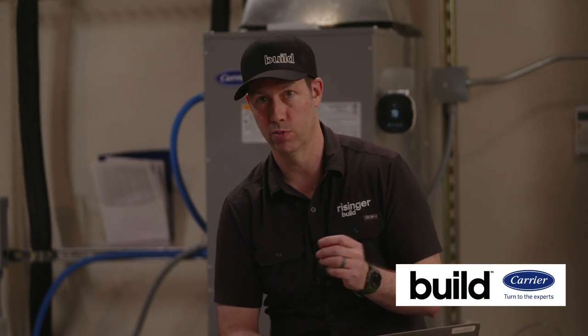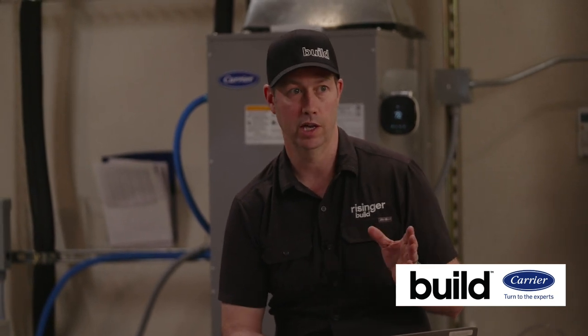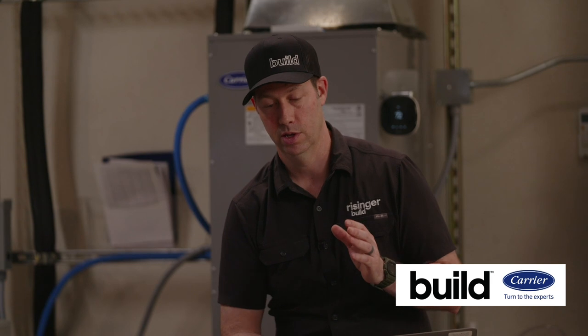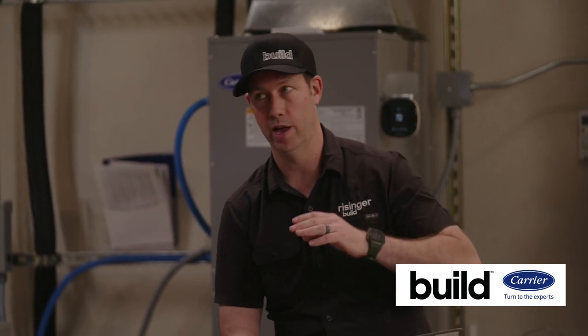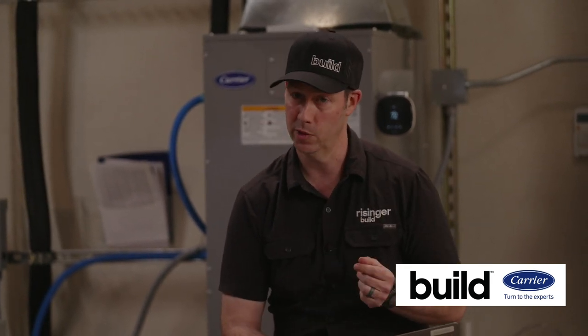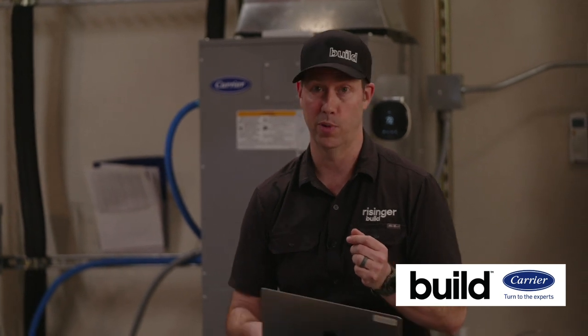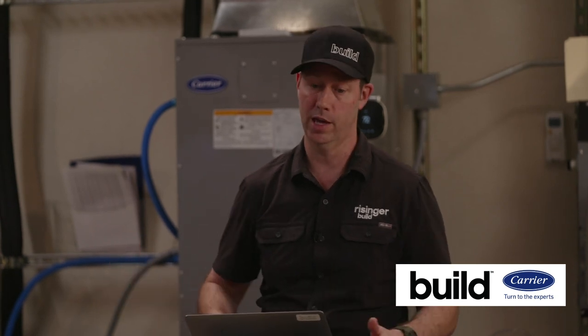On the economic side of going all heat pump and eliminating gas, ask your plumber to break out his bid and eliminate the gas connections. That black iron pipe running through your attic and house is not inexpensive. It's very labor intensive—the pipe itself is cheap, but they're threading it, putting it together. It usually takes the plumber 1 to 2 days with 1 to 2 guys to run all the gas piping for a house. So eliminating that can be a savings you could put toward other things in the house.